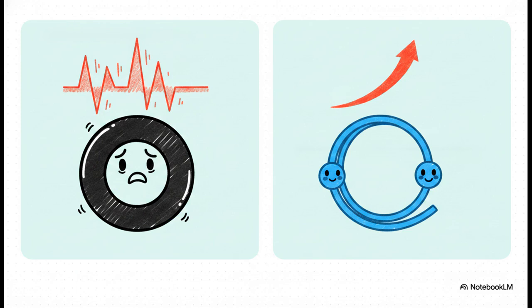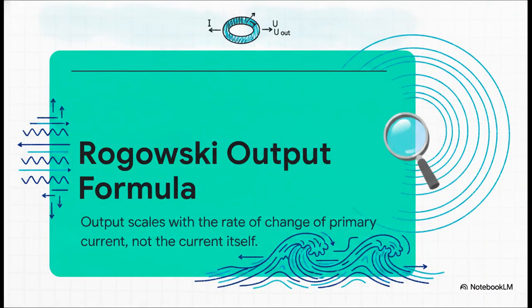Now compare that to the modern solution, the Rogowski coil. This is a real game changer. It's a flexible, non-magnetic winding. And because it totally lacks an iron core, it has zero saturation and zero hysteresis. That means its output stays perfectly linear across the full current range, no matter how wild or chaotic the fault spike gets. And this formula brilliantly illustrates the physics behind why it works so well.